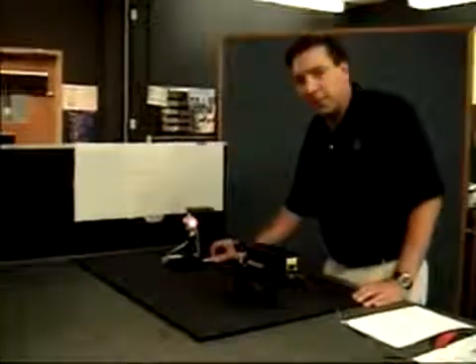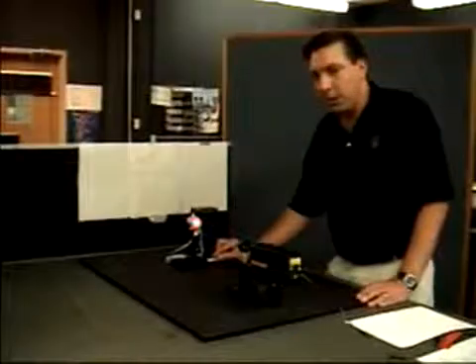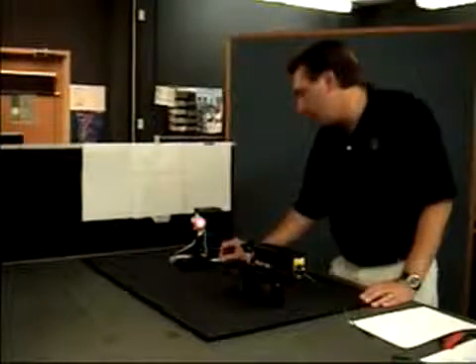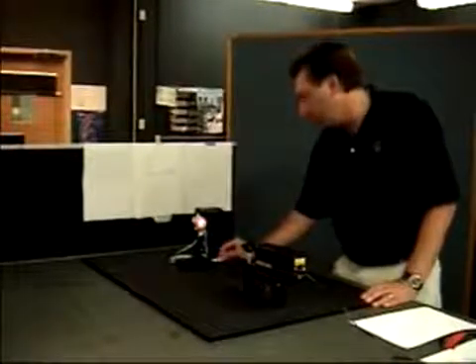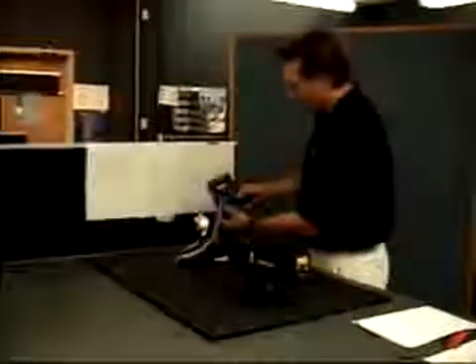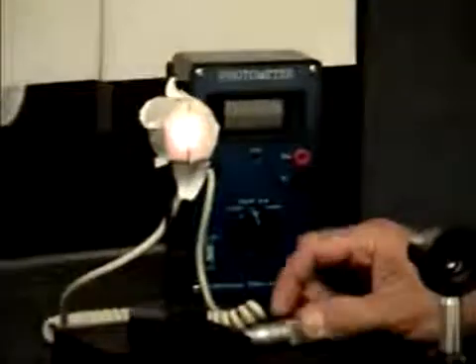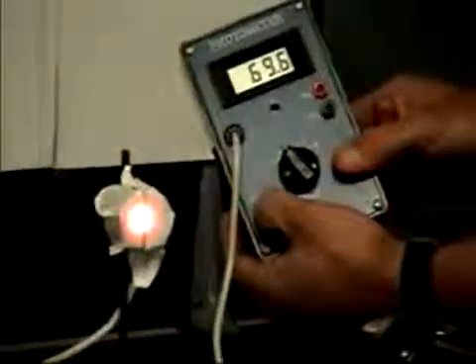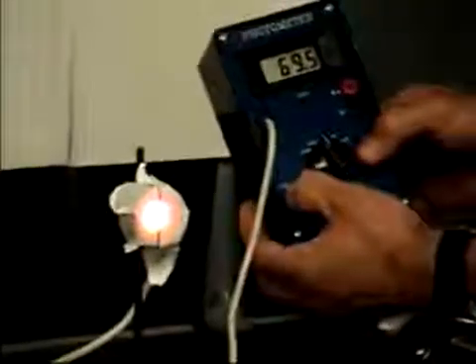The camera cannot focus down onto the actual micrometer setting, but two rotations of the knob will give you 50 thousandths of an inch movement. The first measurement, we started out at 75.7 and the intensity has dropped down to 71.9 roughly. We are going to take that reading, then move it another two rotations or 50 thousandths of an inch, and take another reading. It appears that we have gotten down to 69.5 units.